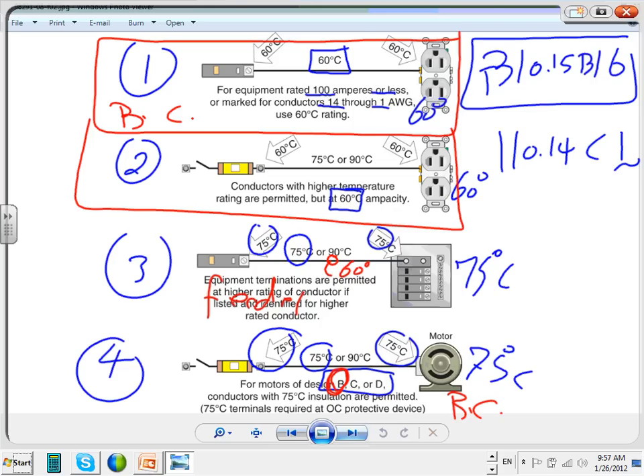We always say motors are an exception to rule 1. Yes, absolutely. But it's still though, this comes by design 75, this has to be 75, but the cable has to be 75 to apply the exception. Yes, Nick? I was just going to say, because motors, we normally use 75. Yeah, based on this exception. And all this information is summarized, guys, in 110.14(C)(1). And the table that we're looking at is 310.15(B)(16) and other tables, but the most common one is 310.15(B)(16). Any question about this? Can I get you to understand this 60, 60, 60? We're talking about branch circuits here, excluding the motors.